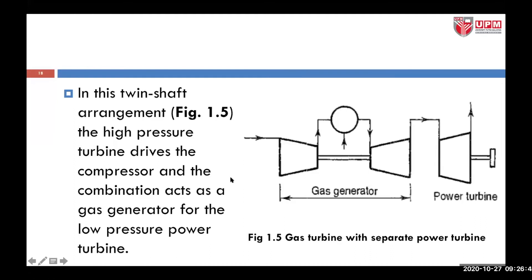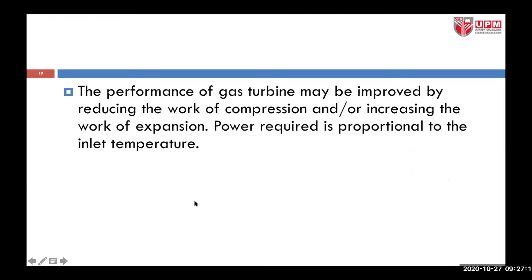In this twin shaft arrangement, figure 1.5, the gas turbine has a separate power turbine. We have a case where the compressor is connected via a single shaft to the turbine — this is what we call the gas generator — and it is coupled with a power turbine, another turbine set separately. This combination acts as a gas generator for the low-pressure power turbine.